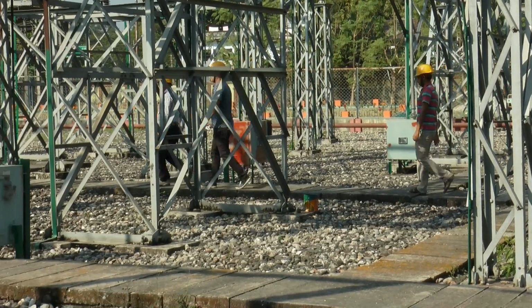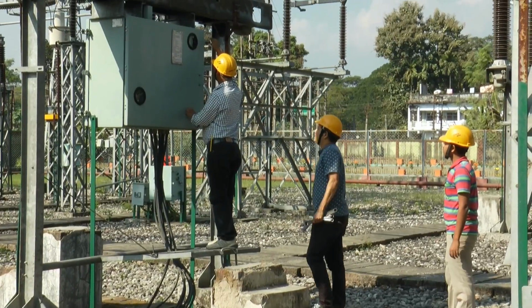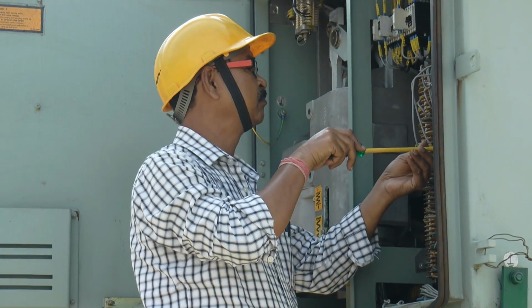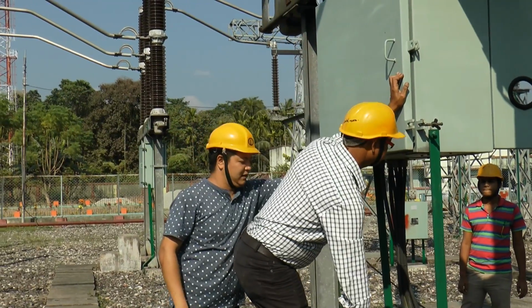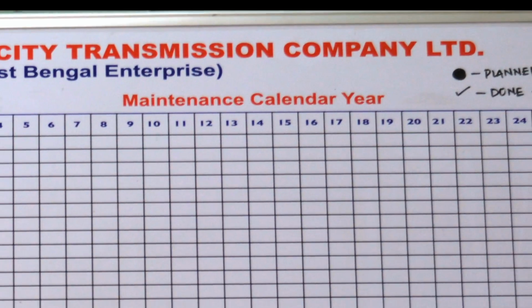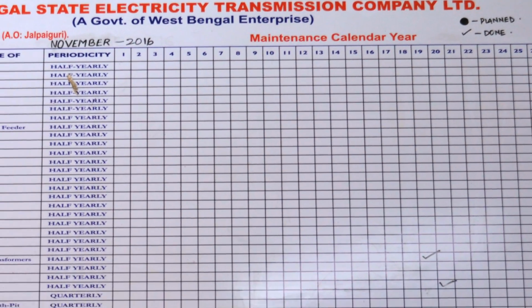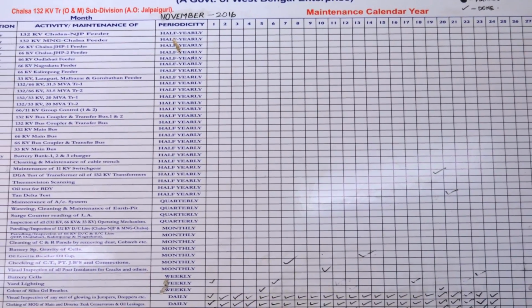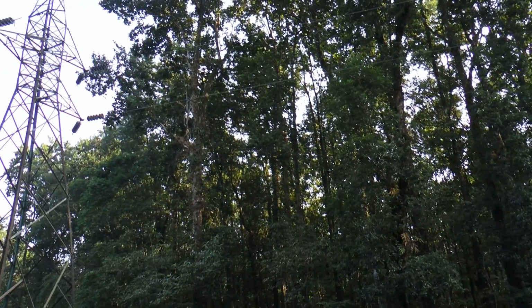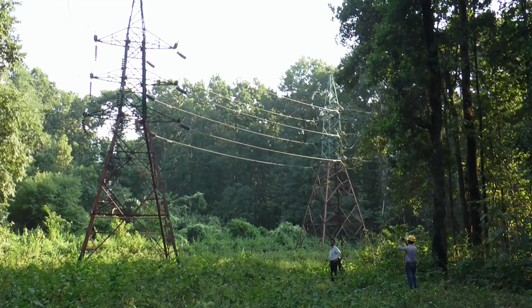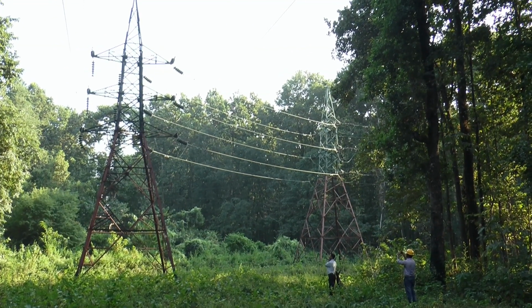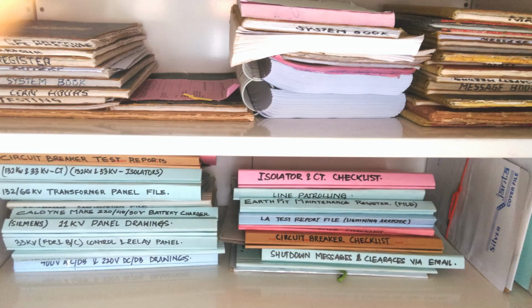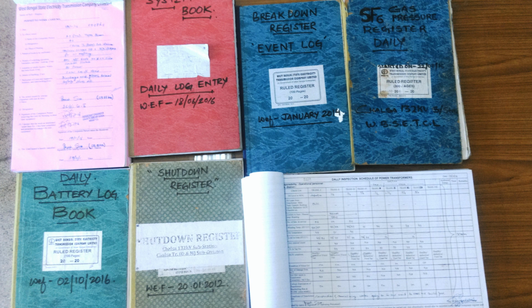Periodic maintenance of substation equipments as per maintenance schedule is conducted to provide proper functioning of equipments, and standard operating procedures are duly followed to avoid incidents. Maintenance calendar is kept in the control room and advanced planning is done for monthly maintenance and is indicated in the calendar. Periodic line patrolling and tree cutting of lines are done to ensure uninterrupted power supply by avoiding outage and breakdowns. The different types of registers, records and files are maintained regularly and kept in the control room. Example: system book, battery, shutdown and breakdown registers, permit to work, daily inspection book, etc.